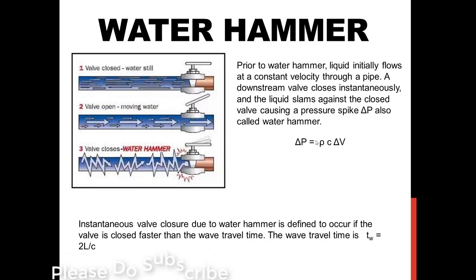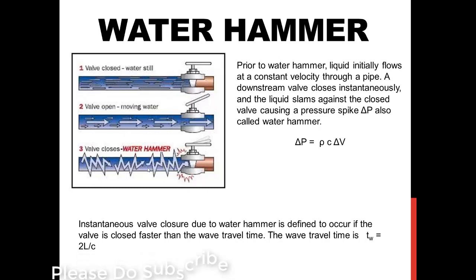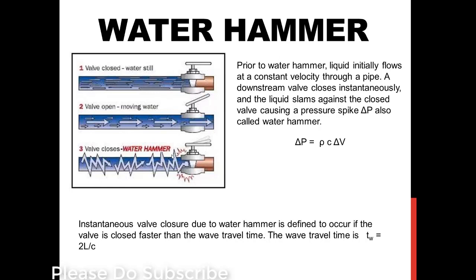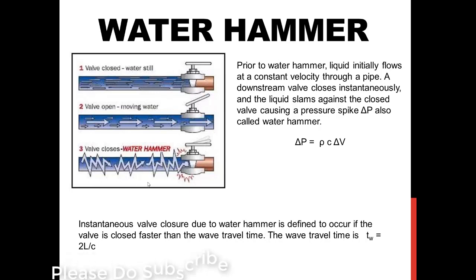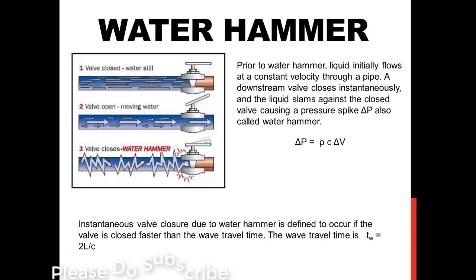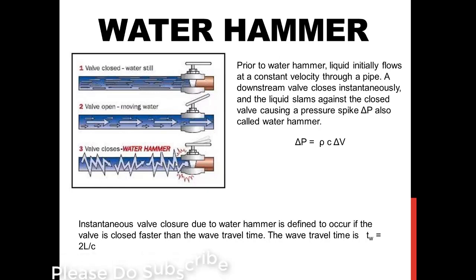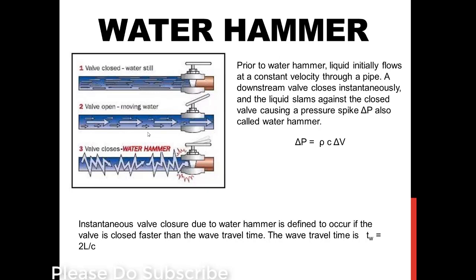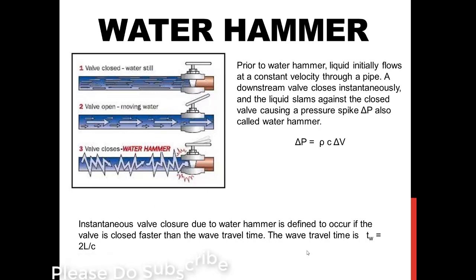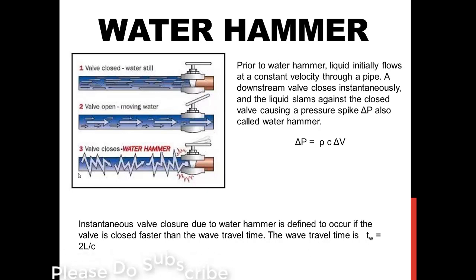The density is a variable with respect to space because it is a compressible fluid. In order to have this pressure wave get transferred within the fluid, we need to have the compressibility effect. Otherwise we cannot have the wave motion to transfer in the water. Instantaneous valve closure means that the valve closure time should be equals to 2L by C. L is the length through which it needs to travel and C is the velocity of sound.